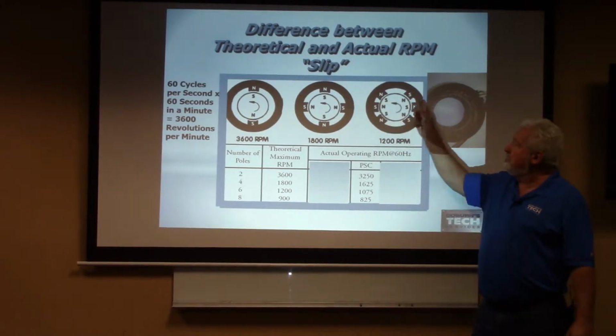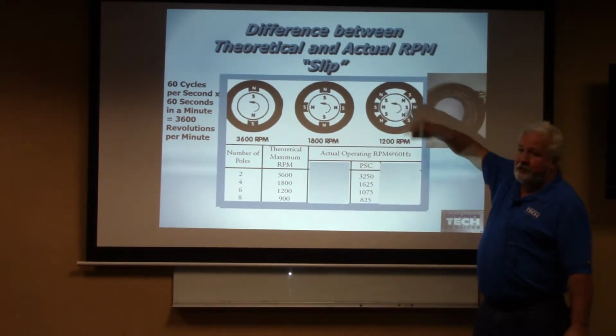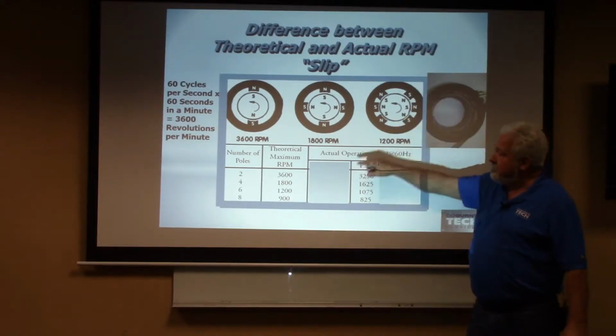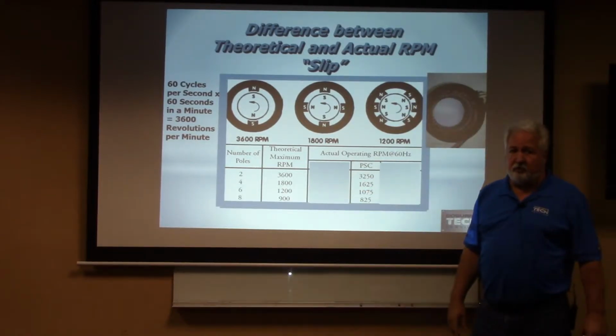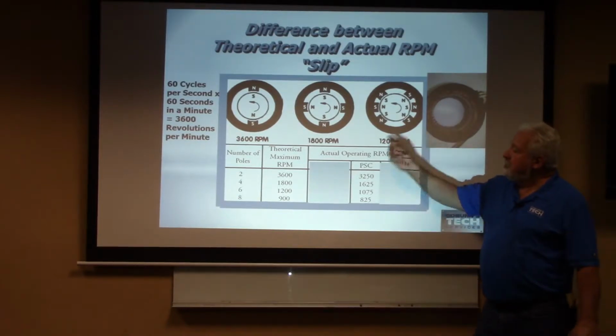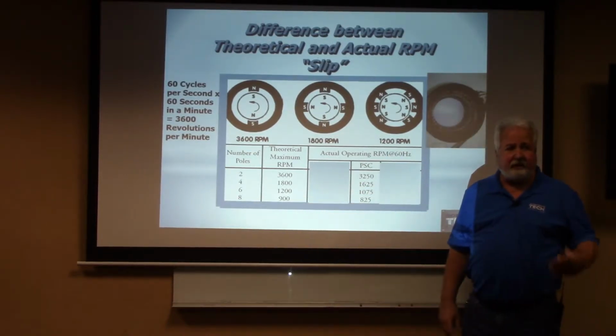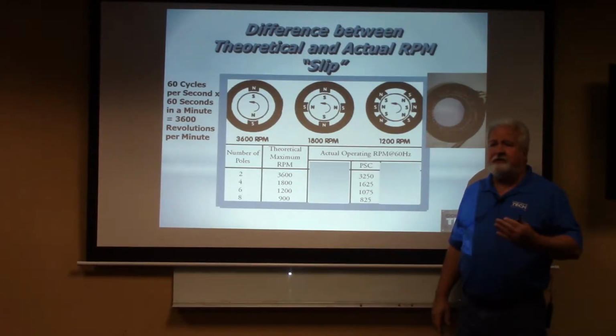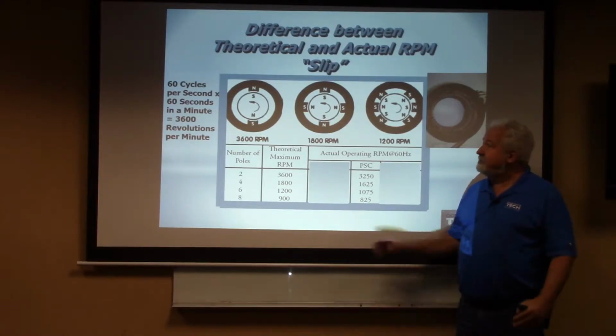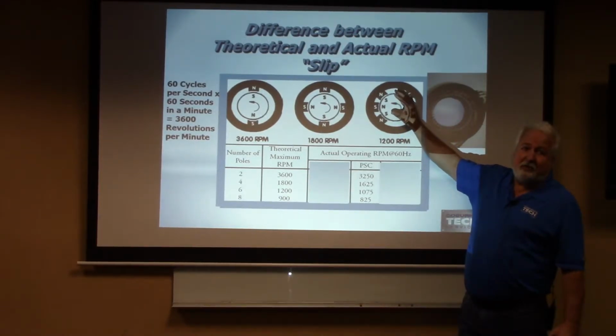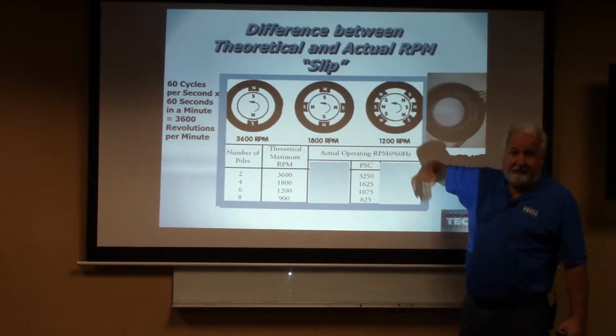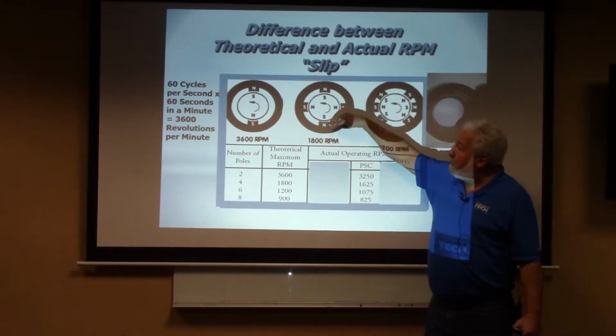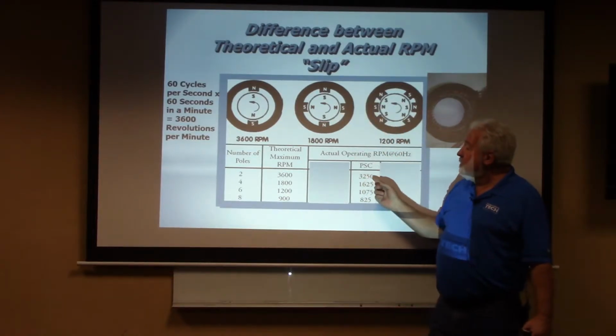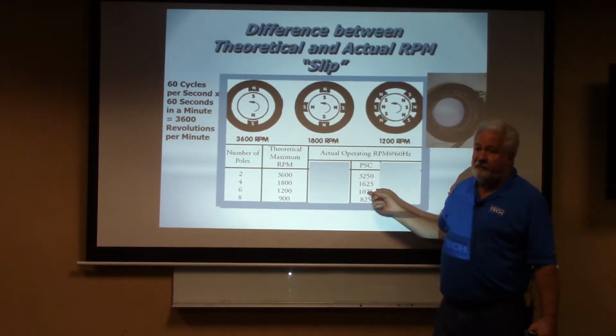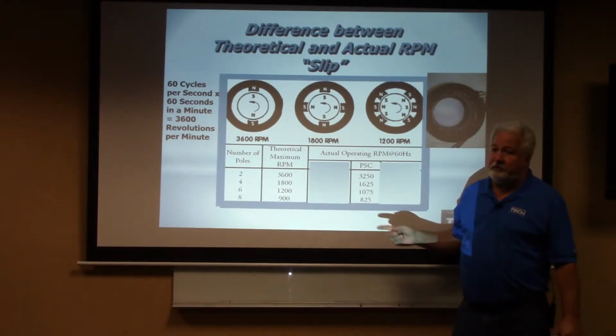A 6-pole motor, it's only going to move this far each cycle of that frequency. When I do that, now I'm down to about a 1,200 RPM motor. 8-pole motor, we would see down to about 900 RPMs. Now that's theoretical. Basically it's saying in theory that's how fast it was going to go. Actual, what happens is there's something called slip or drag. It's not really going to make that 1,200 RPMs every time it goes around. What it'll do is now drop down to about 1075. An 8-pole motor is about 825.